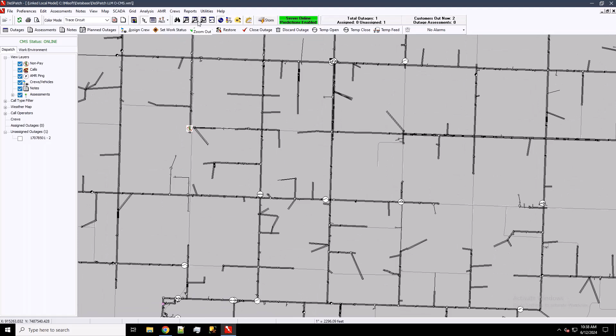This first one, we'll assume we have a feeder operation. This 1103 breaker that we've mapped point 1 to is going to lock open, and when that happens, Novatech will send us that open. Brett, if you want to fire that off now. Yep, sending right now.